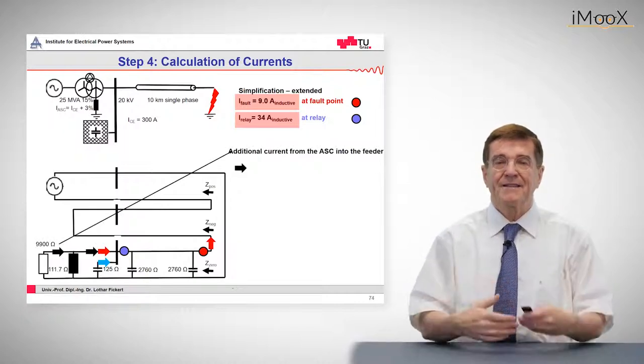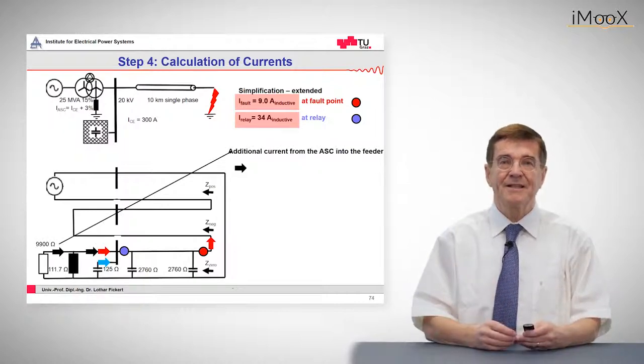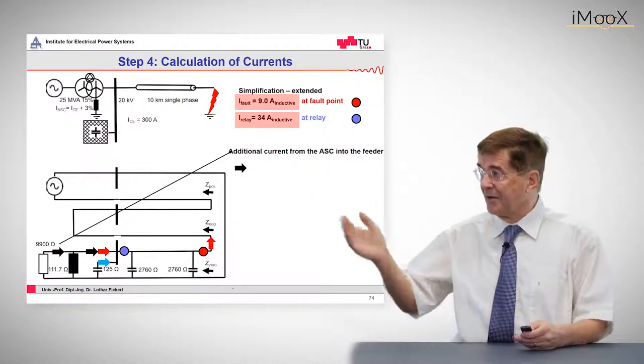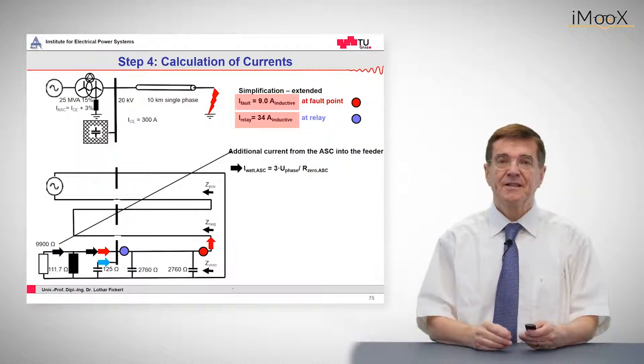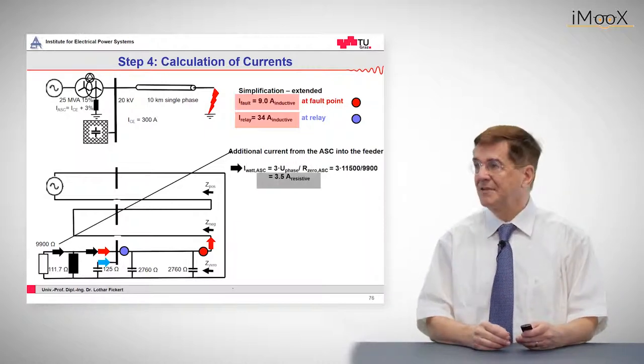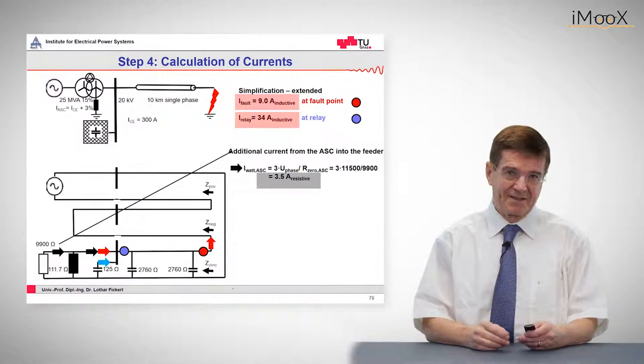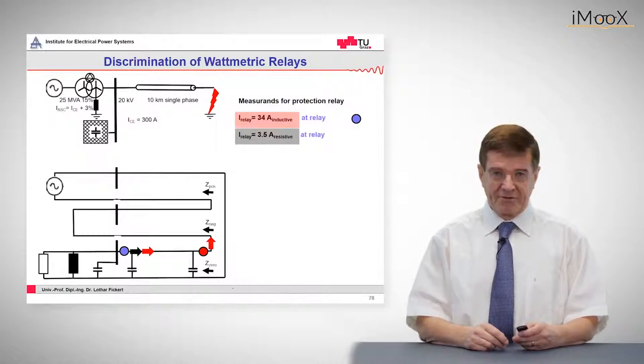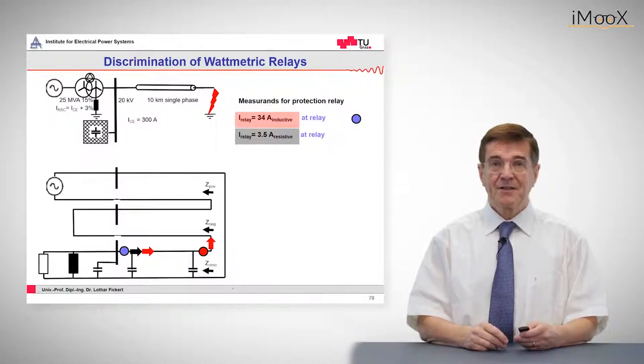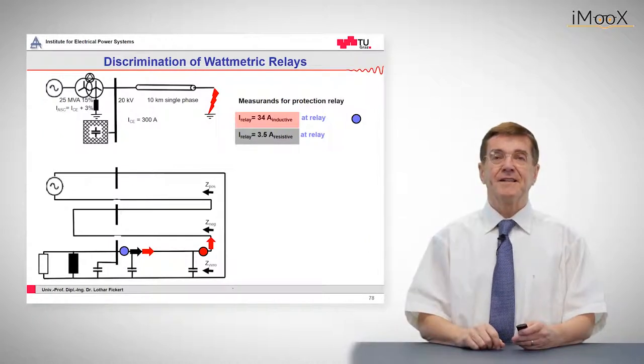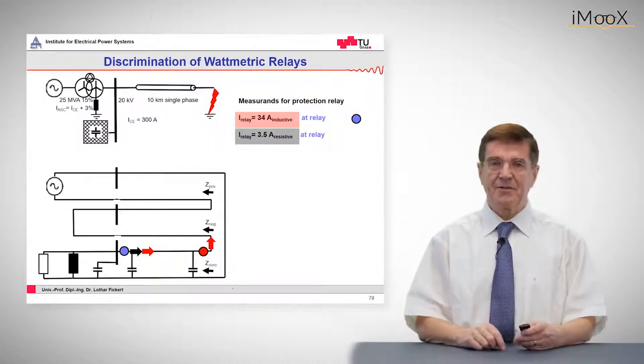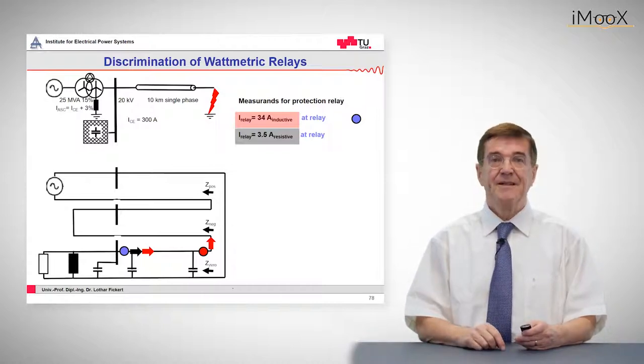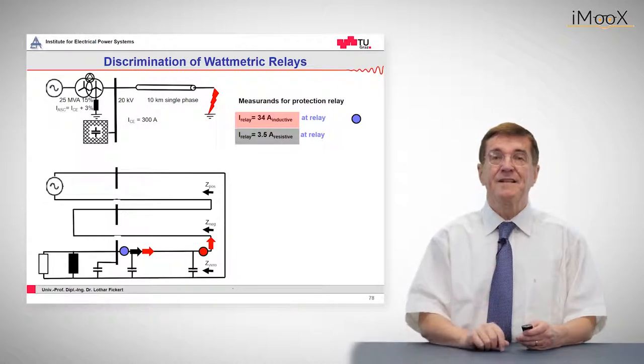And we should add now this normally neglected resistive current, the wattmetric current, which is given by the losses of the arc suppression coil, that comes out as 3.5 amps in the zero sequence system. So as it was shown, the protection relay at the bus bar, looking into the feeder, sees a reactive current of inductive type of 34 amps and a resistive current of 3.5 amps. And the resistive current is the decisive one.